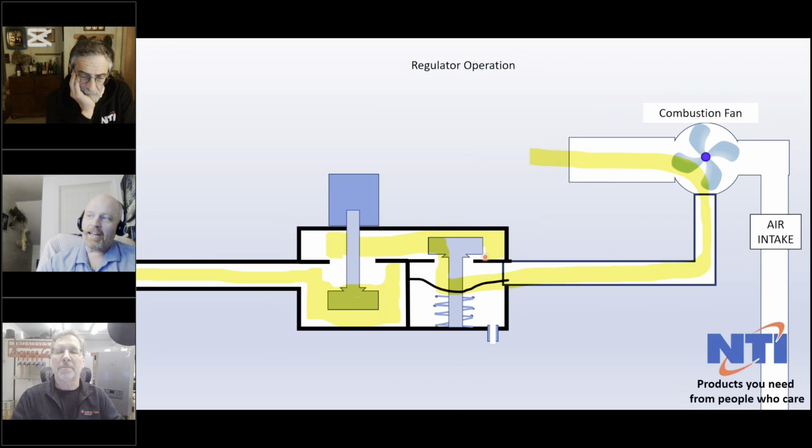So no matter what time of the year you do your combustion analysis, it's not going to change. If you do this in the winter when the air is very dense and the pressure is higher, it's going to regulate itself to be the correct mixture, just as when we have a hot day and the air's thinner.